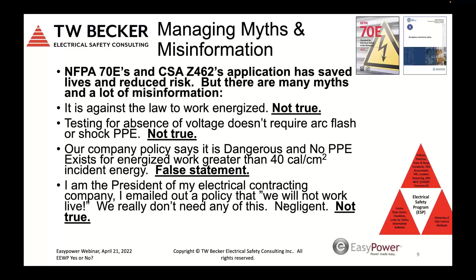But it does relate to this: well, can we do energized work? When do we need the permit, right? The next one says, I'm the president of my company, my contracting company. I just emailed a policy that we don't work live here. Well, that's actually a negligent statement, because every electrician has a test instrument and does voltage measurements to test for voltage or test for absence. All energized electrical equipment is inherently high likelihood of having an arcing fault. Well, that's not true either. Arc blast pressure will pulverize you.